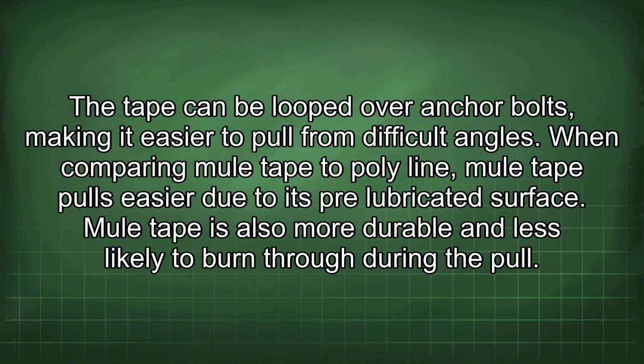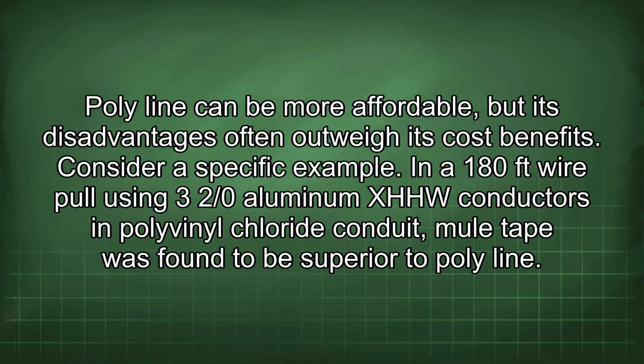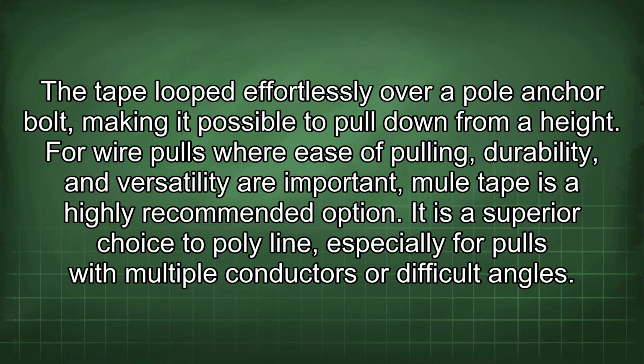When comparing Mule tape to polyline, Mule tape pulls easier due to its pre-lubricated surface. Mule tape is also more durable and less likely to burn through during the pull. Polyline can be more affordable, but its disadvantages often outweigh its cost benefits. Consider a specific example. In a 180 ft wire pull using three 2/0 aluminum XHHW conductors in polyvinyl chloride conduit, Mule tape was found to be superior to polyline. The tape looped effortlessly over a pole anchor bolt, making it possible to pull down from a height.